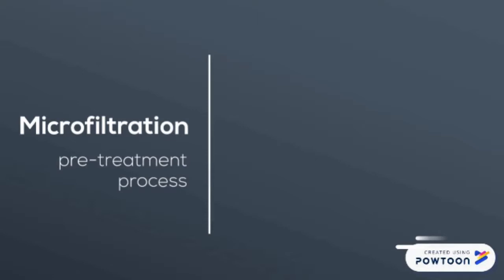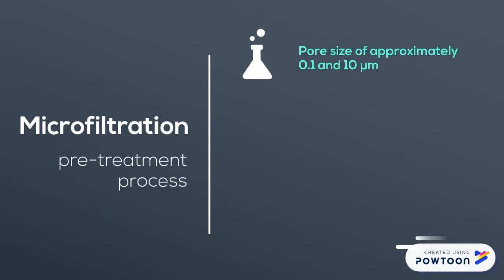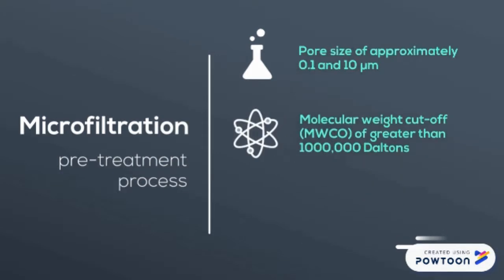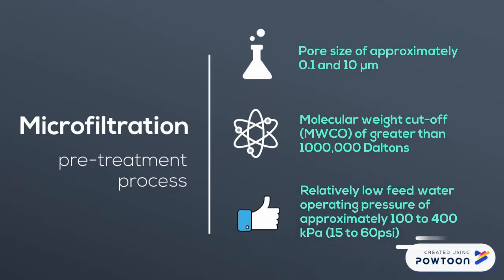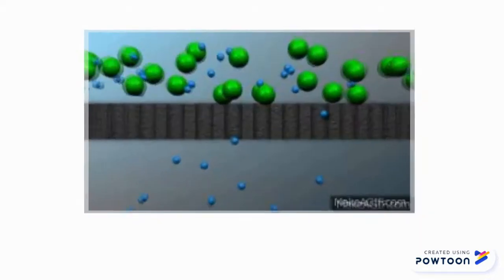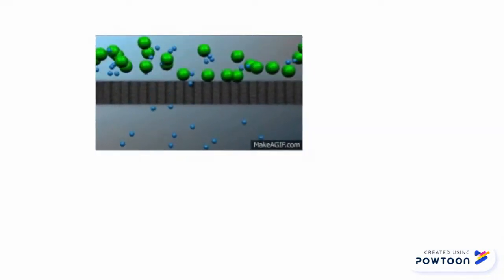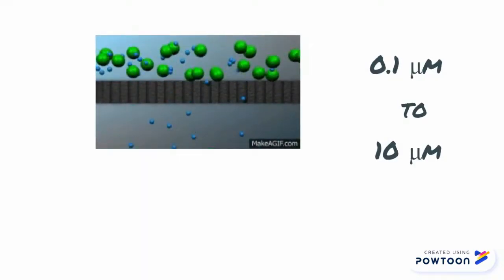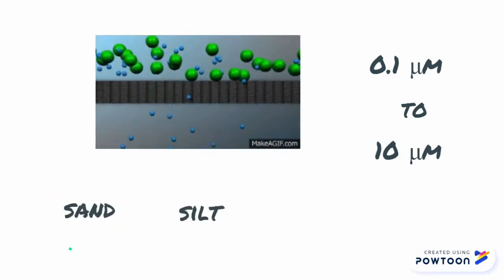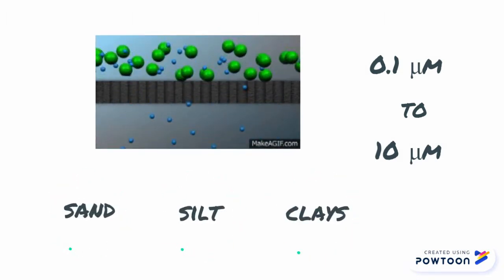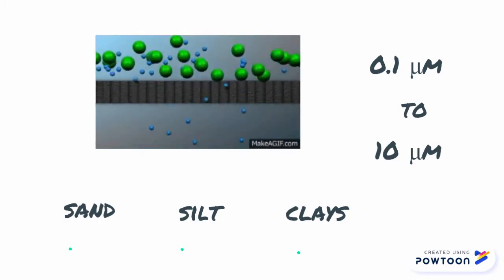Microfiltration is a membrane separation that usually serves as a pre-treatment process for other separation processes such as ultrafiltration and nanofiltration. The separation process is carried out using membranes with a pore size of approximately 0.1 to 10 micrometers, a molecular weight cutoff of greater than 1 million daltons, and a relatively low feed water operating pressure of approximately 100 to 400 kiloPascal. Since the pore size is approximately 0.1 to 10 micrometers, microfiltration membranes fall in between ultrafiltration membranes and conventional filters, making them suitable for separating large-size materials such as sand, silt, and clays.